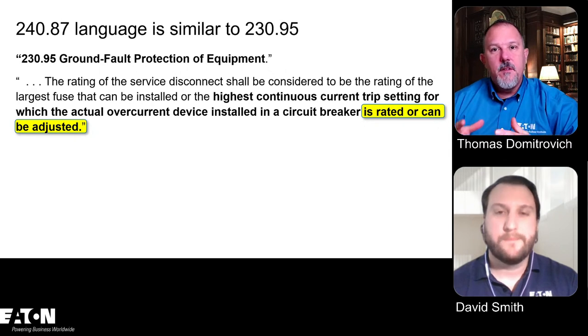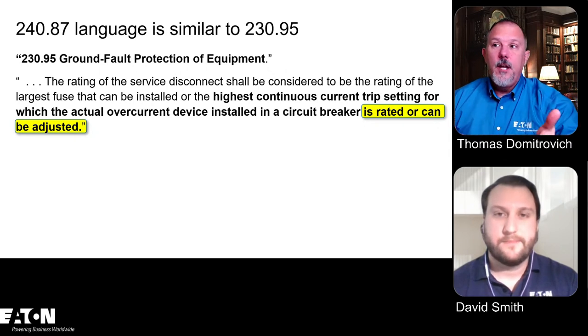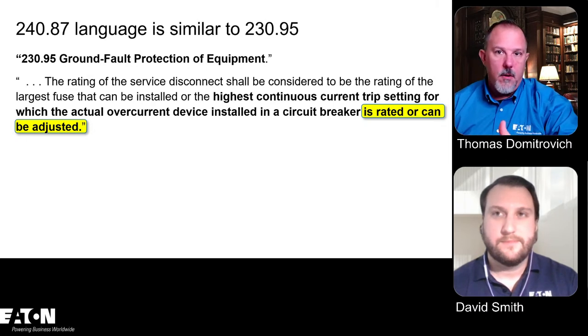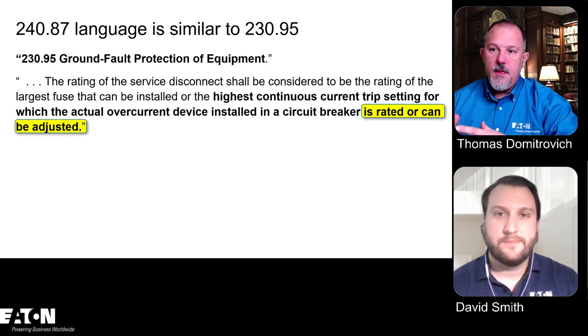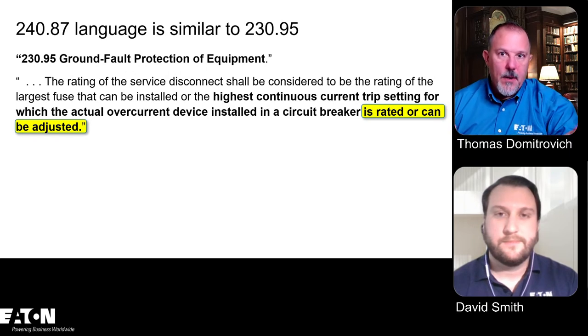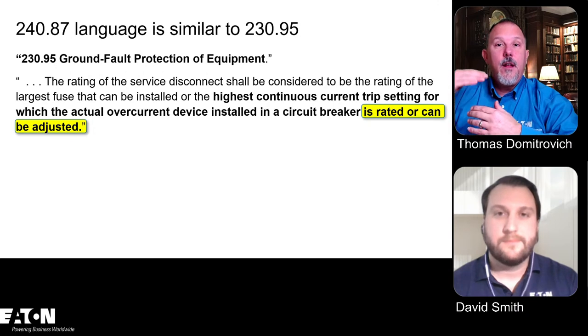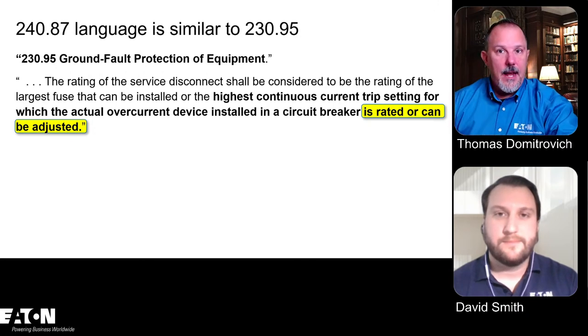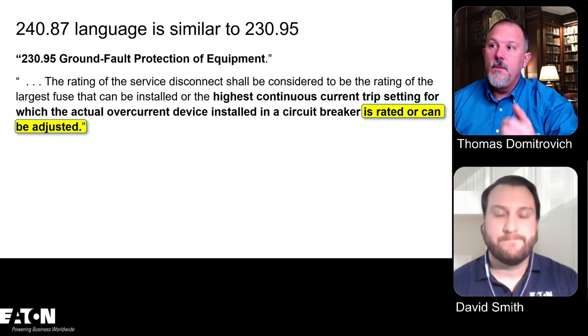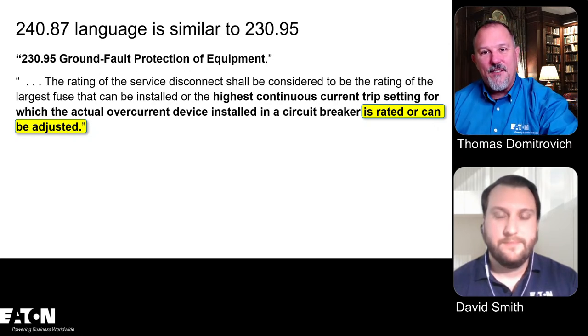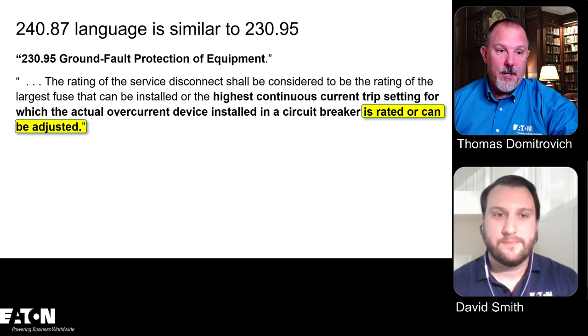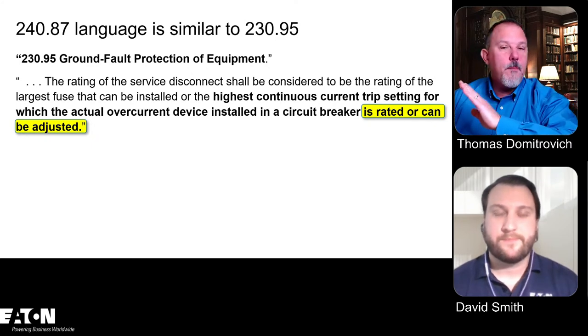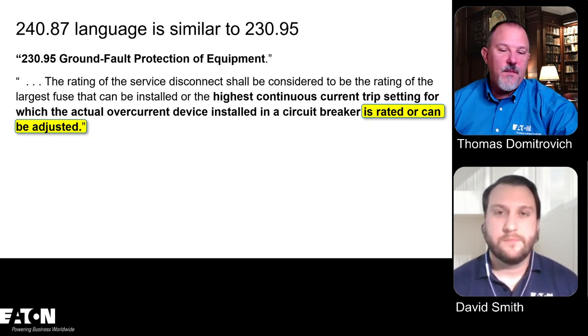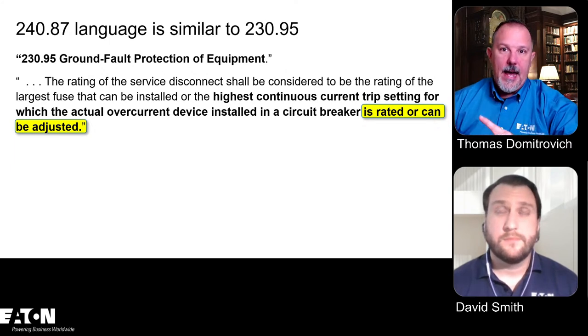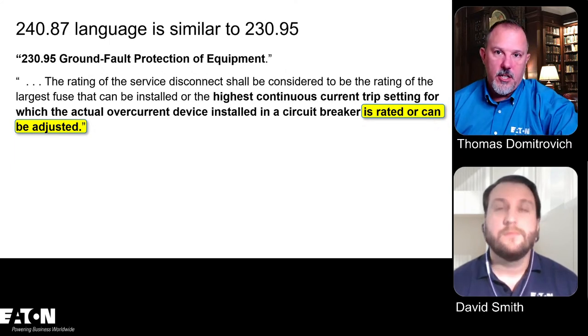In the first draft of the meeting, they changed the language because they realized that 240.87 only impacted a very small amount of circuit breakers, and that there are insulated case circuit breakers and molded case circuit breakers that are large and provide a delay that will have a lot of incident energy through.